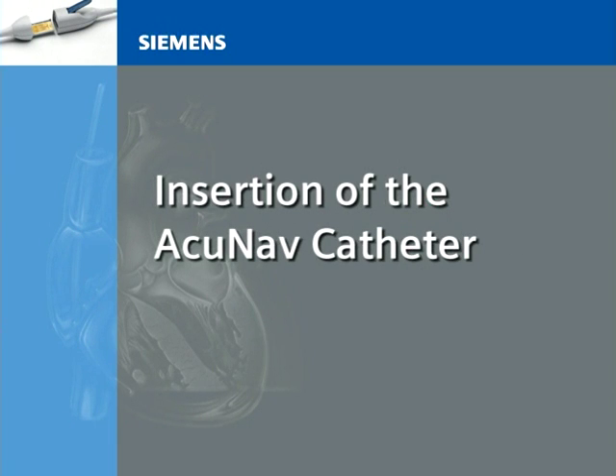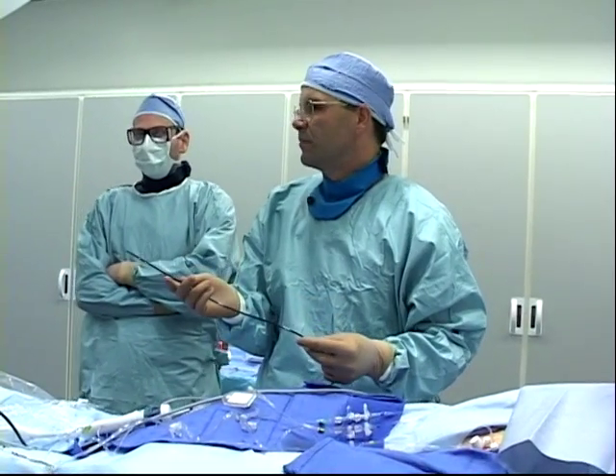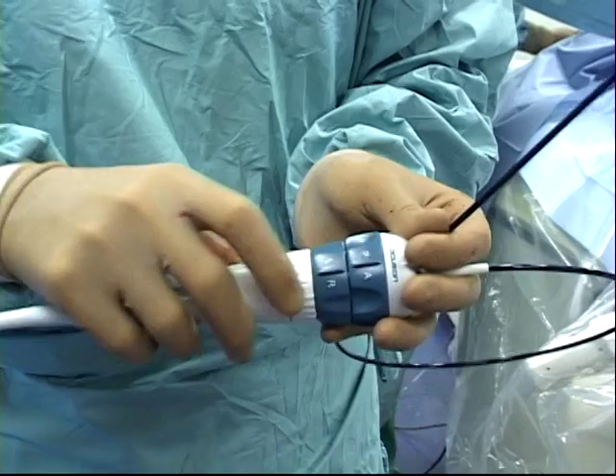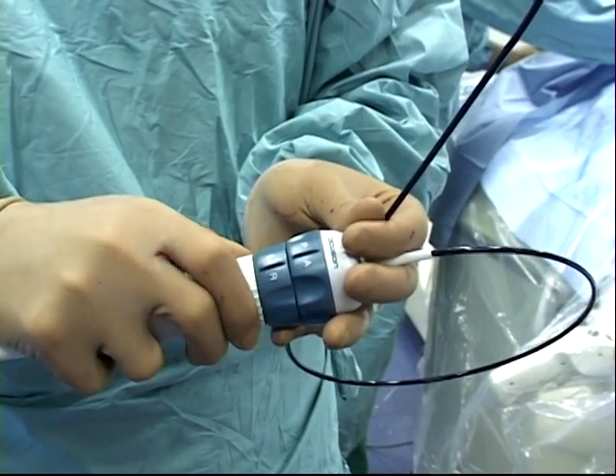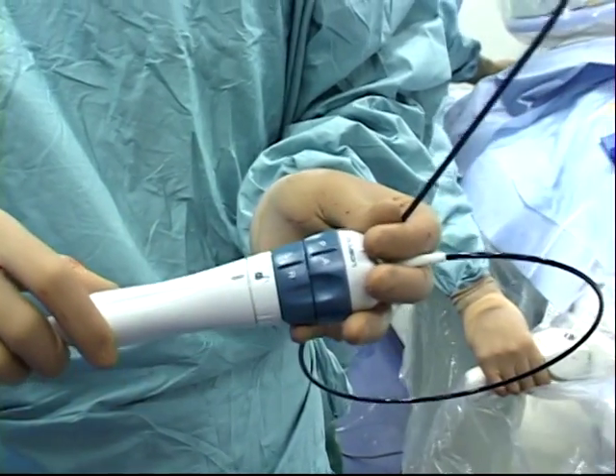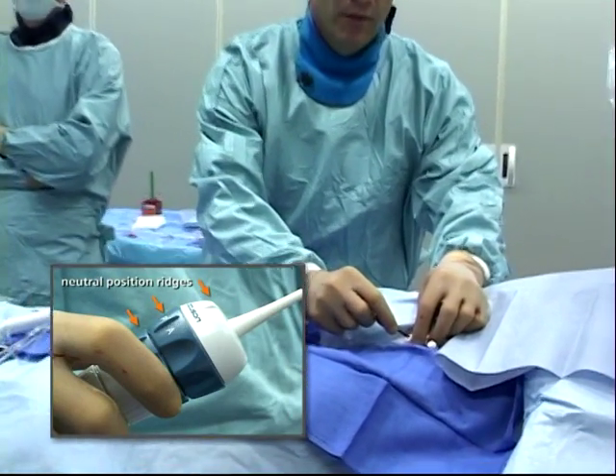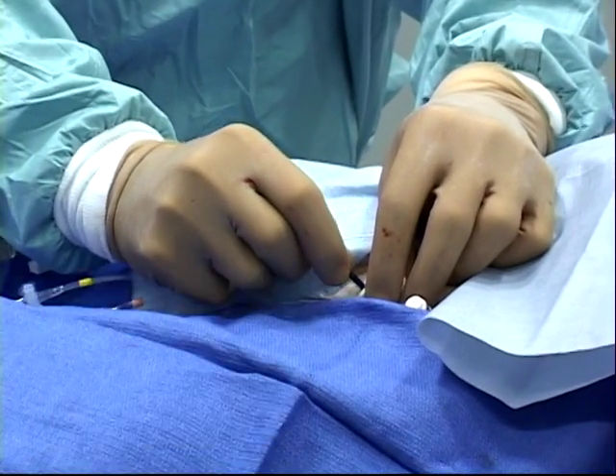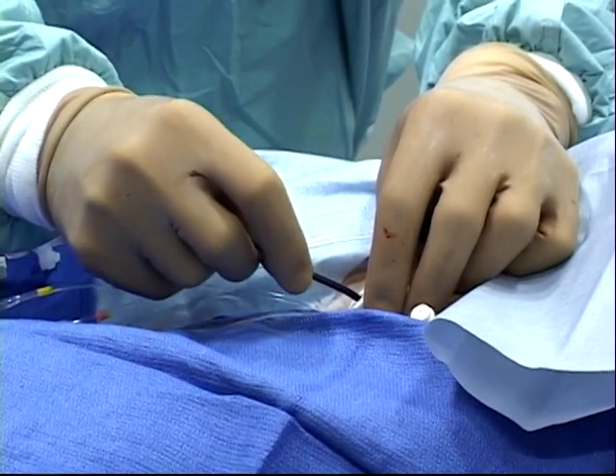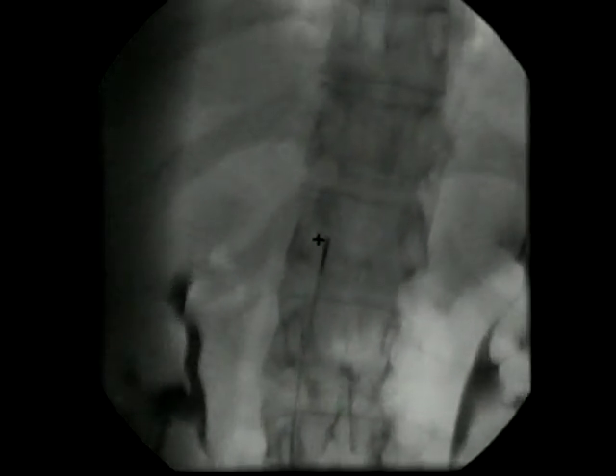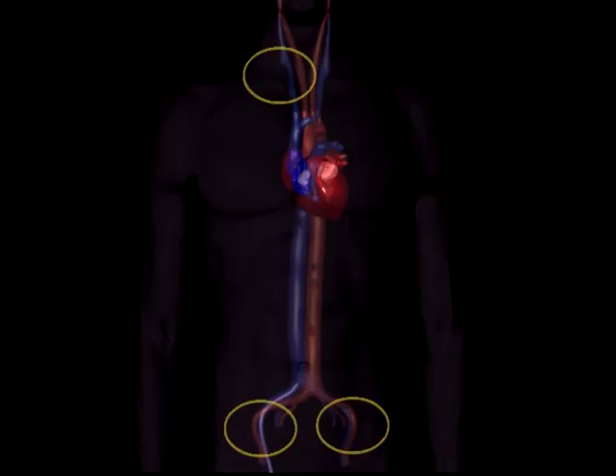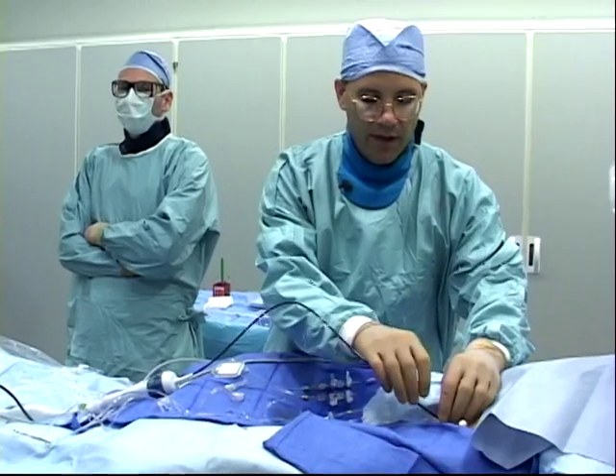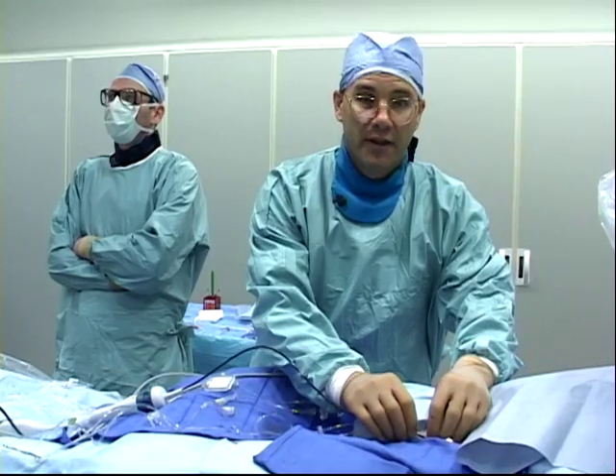Insertion of the AcuNav catheter. Before advancing or withdrawing the catheter, always ensure that the tip of the catheter is straight and that the tension control knob is set at low tension so that the tip of the catheter can move freely. Insert the tip of the catheter into the venous introducer with the neutral position ridges on the two steering knobs aligned with one another and facing up. Do not use excessive force to advance or withdraw the catheter. Fluoroscopic guidance may be helpful in advancing, steering, and withdrawing the catheter. Either the left or right femoral veins or the internal jugular vein are typically used for insertion of the AcuNav catheter. A physician trained in cardiac catheterization should determine the optimal insertion point.